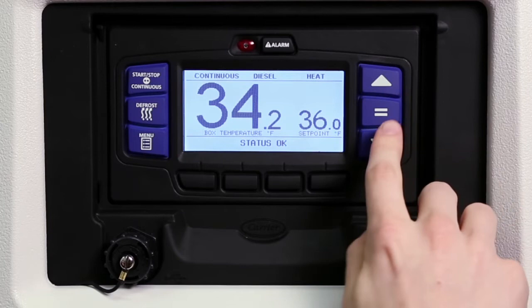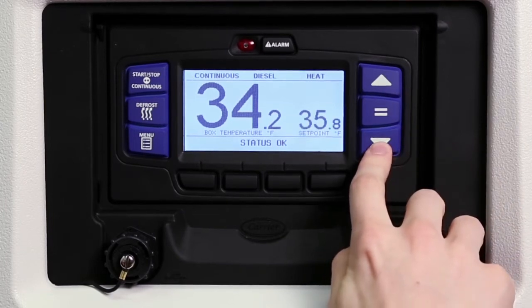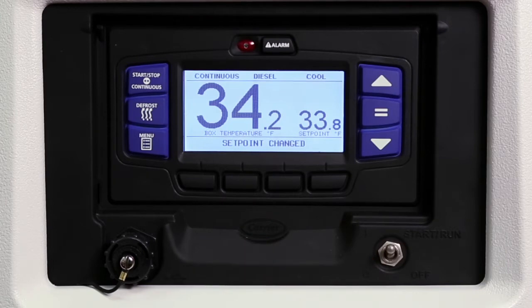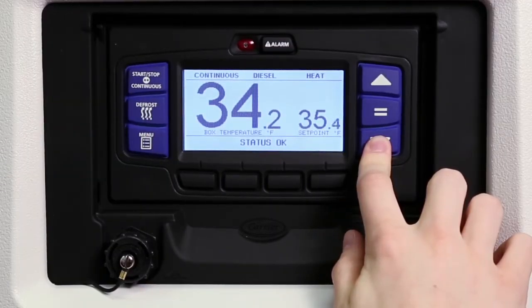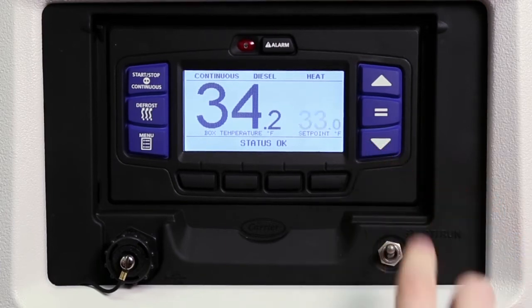Depending on the specifications of the load you're carrying, it may be necessary to change the set point. To change the set point, press the up or down arrow keys to the desired set point temperature. To save the new set point, press the equal key. The message center will display 'set point changed.' If the equal key is not pressed, the set point screen will flash and revert back to the original set point.